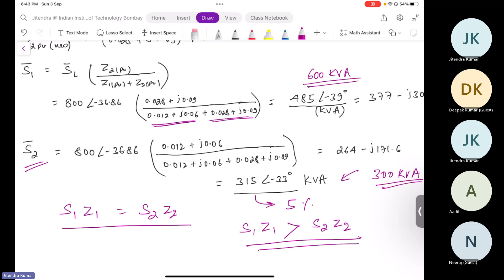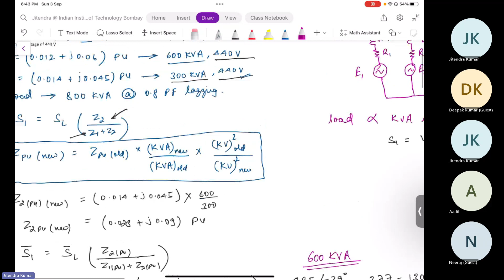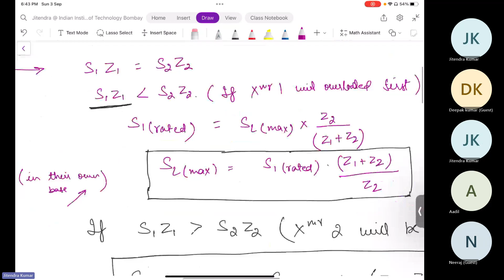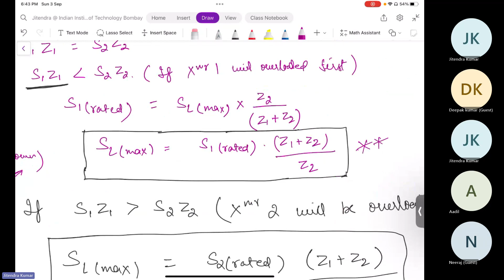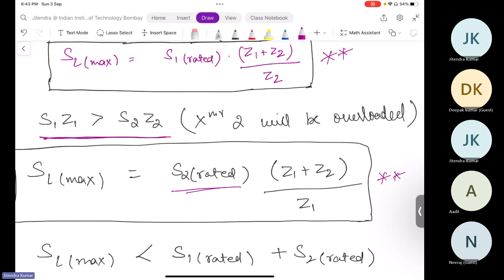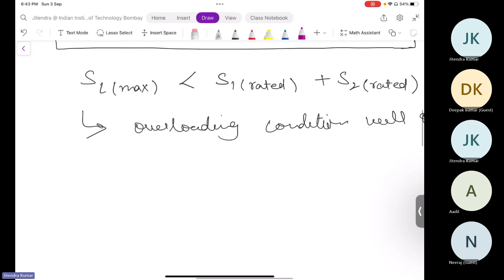Now, the important thing is how much load should have been there such that the second transformer would not have got overloaded. For this purpose I have derived this expression, if you recall. And here the second transformer is getting overloaded, so we have to consider this case, when S1Z1 is greater than S2Z2, as I told you. Now we have to identify SL max, the maximum load that can be catered without overloading of any transformer.